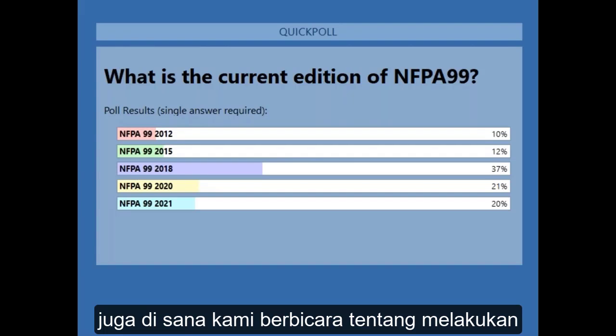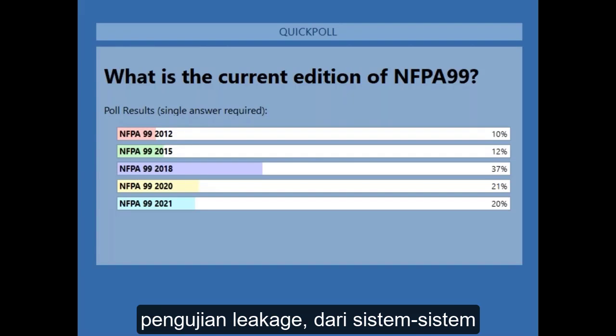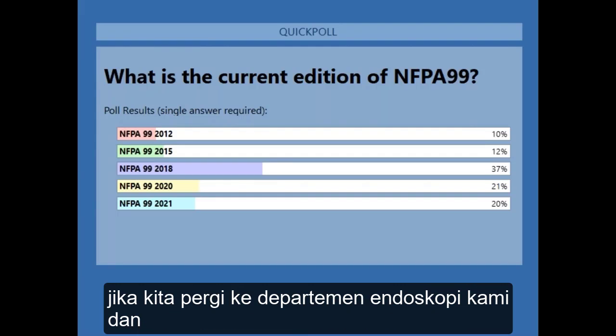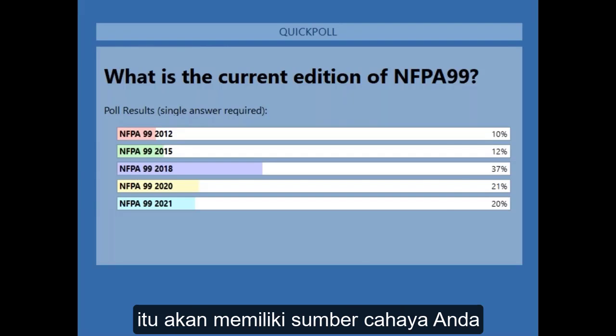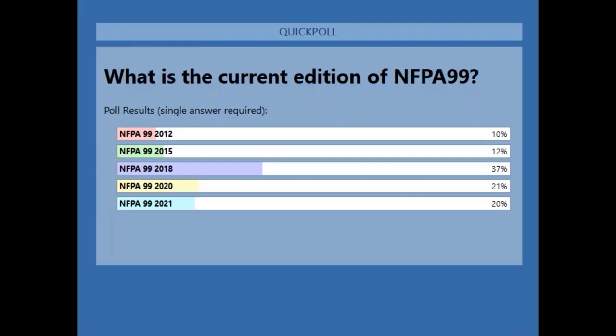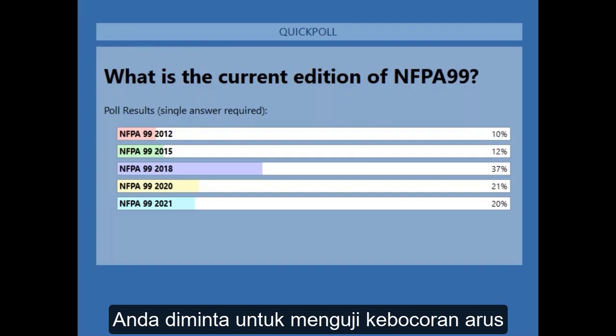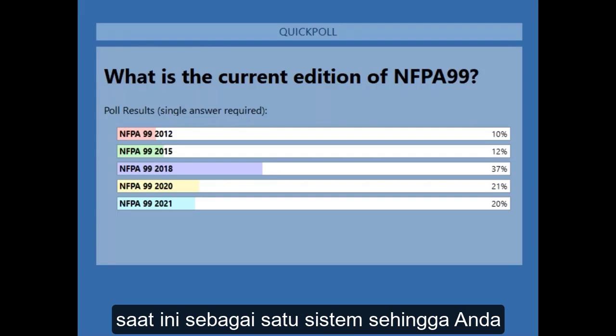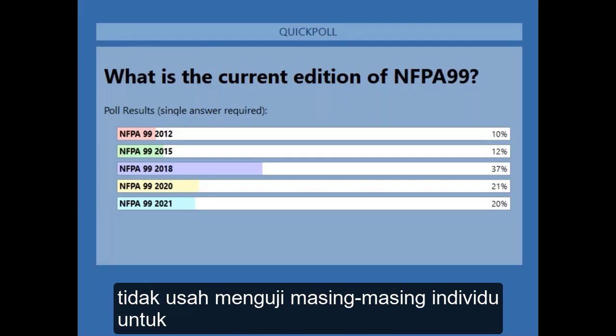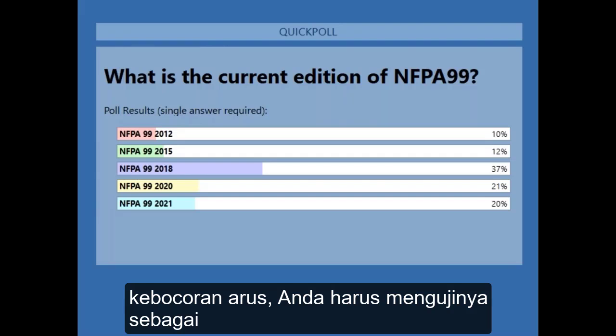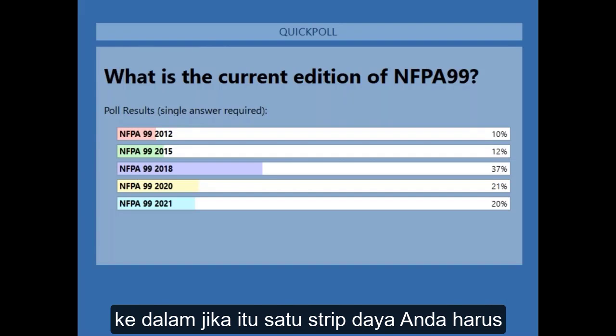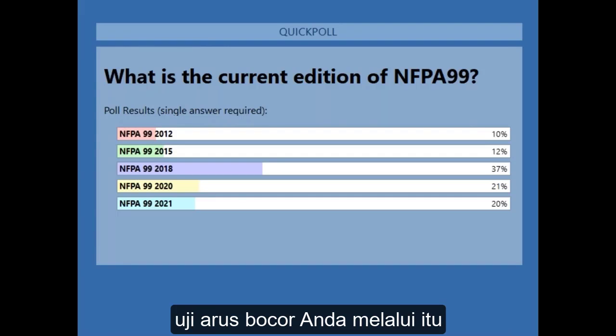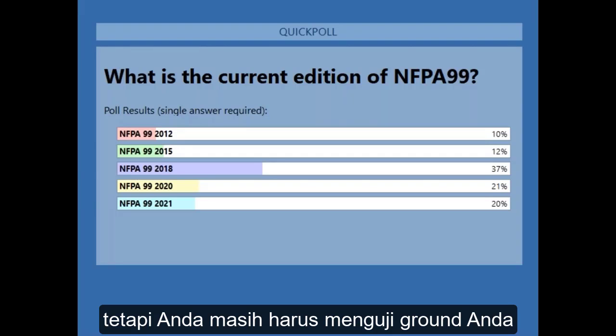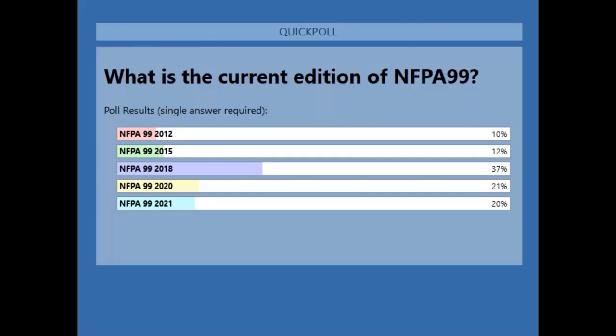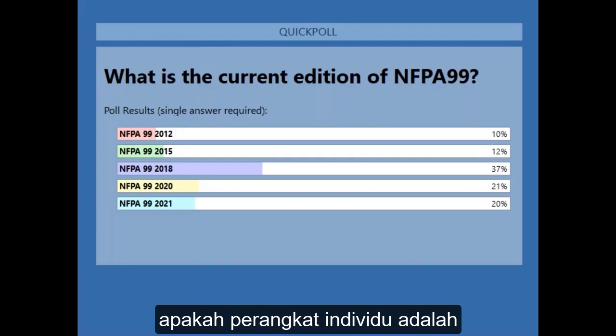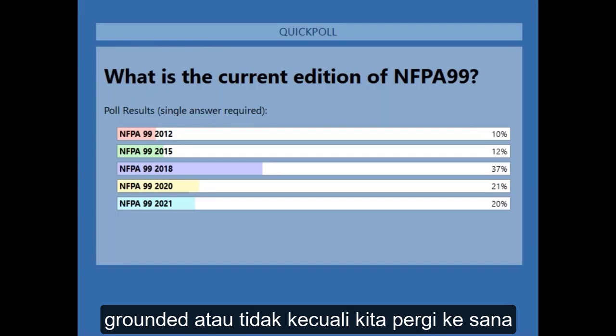Also, when we're talking about doing leakage testing of systems, if we go to our endoscopy department, and there are many in what I call endo towers, it'll have your light source, your endo camera, and a television, your LCD or monitor on top. You are required to test for leakage current as one system. So you don't test each individual one for leakage current. You have to test it as one system. So whatever that's plugged into, if it's one power strip, you have to test your leakage current through that. But you still have to test your ground to each individual device, because we don't know whether the individual device is grounded or not unless we go to that.